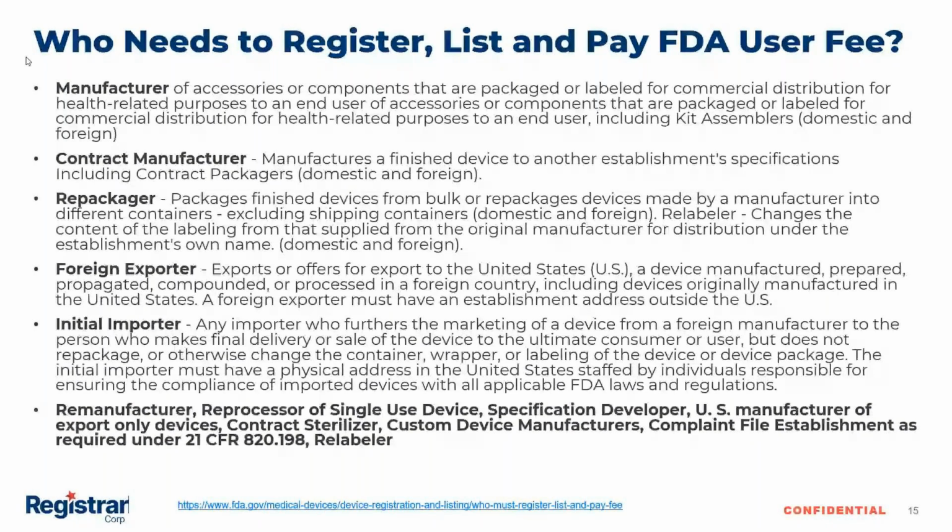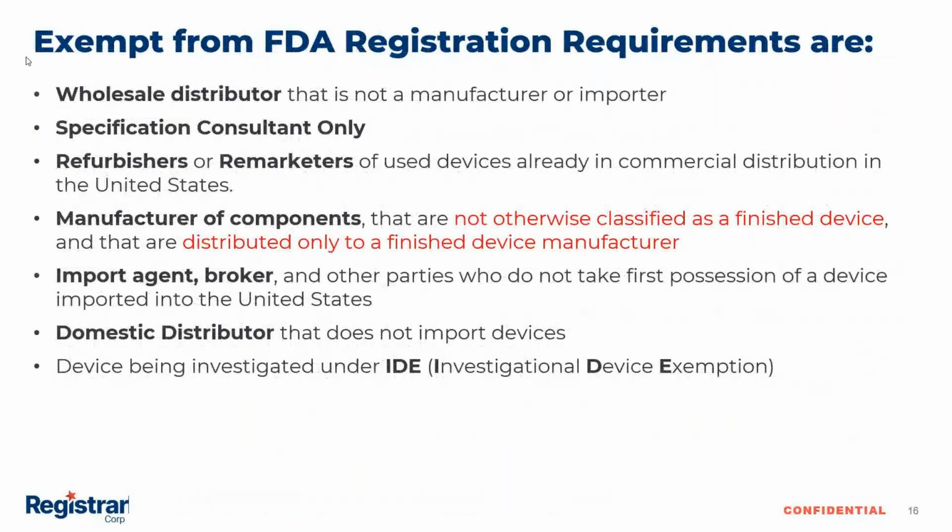There are also a couple of exemptions from FDA registration requirements, like the wholesale distributor. That is not a manufacturer or importer. As long as you only distribute and you possibly buy your products from a US manufacturer and you sell on the US market, then there is no requirement to register your establishment.